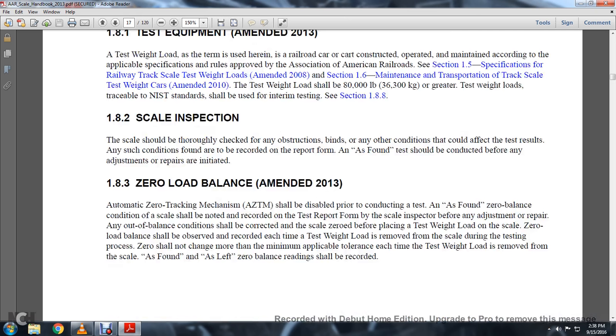1-8-3: Zero Load Balance, Amended 2013. The automatic zero trace tracking mechanism shall be disabled prior to conducting the test as found. The zero balance condition of the scale should be noted and recorded with the test report by the scale inspector before adjusting or repairing.